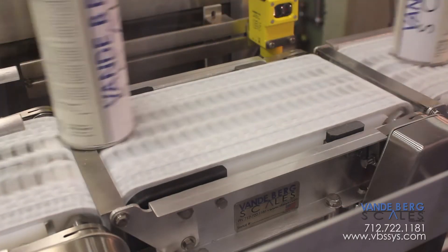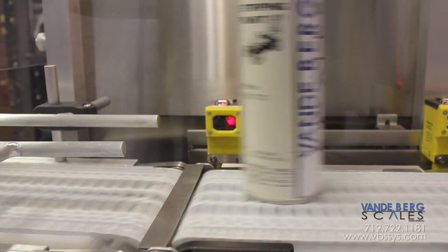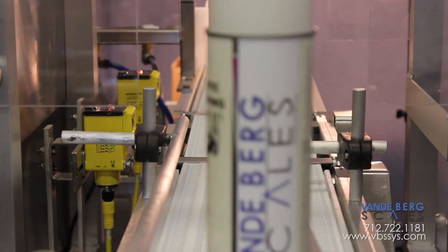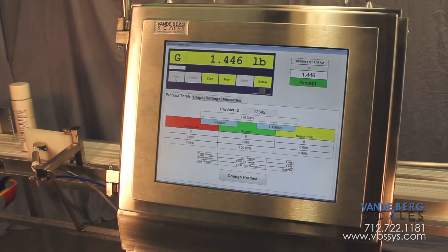But product movement introduces vibration. Note the slight, inevitable product movement as this aerosol can crosses the transport plate to the conveyor scale. Physical photo eyes detect the presence of the product, but virtual photo eyes wait for the product to stabilize on the conveyor scale, then they start the weight measuring process.